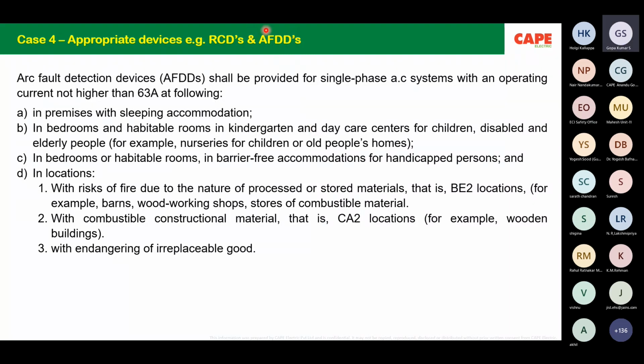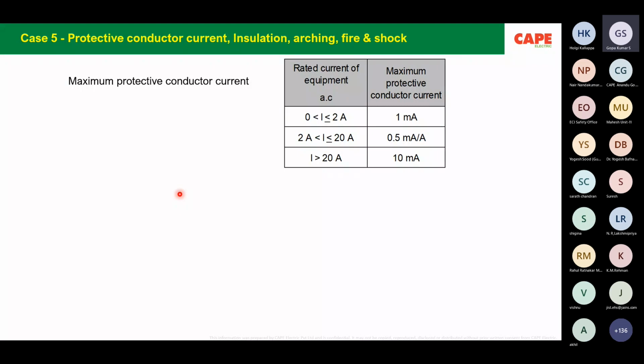again, the other kind of device, AFDD. You are aware that loose contacts and arcings are creating a lot of fire accidents in houses and industrial buildings. So this arc fault detection device is a new device which disconnects the supply in case of any arcing in the circuit. These devices shall be provided for single-phase AC systems with an operating current not higher than 63 amps in premises with sleeping accommodation, in bedrooms, in habitable rooms, and so on. So basically, RCCB and AFDDs are also becoming mandatory in certain cases. We have to go really deep into it. I can explain where this becomes mandatory, but not in this forum. Probably, it needs a lot of time.